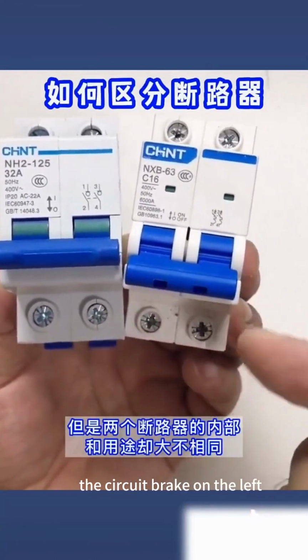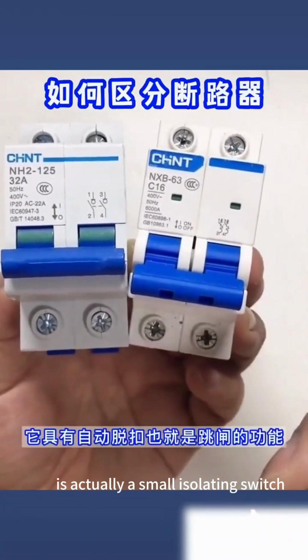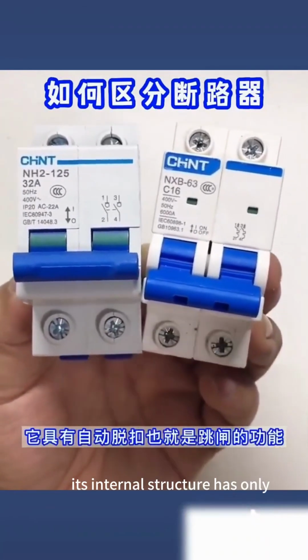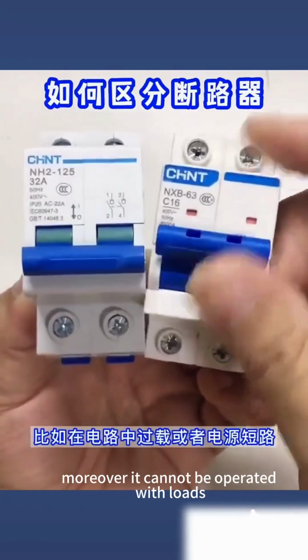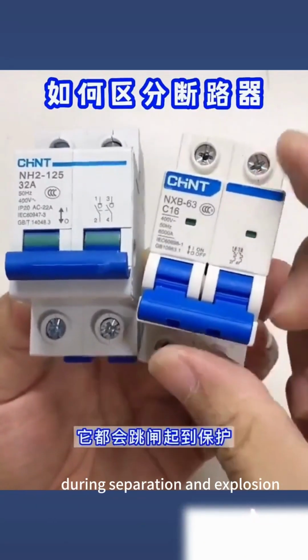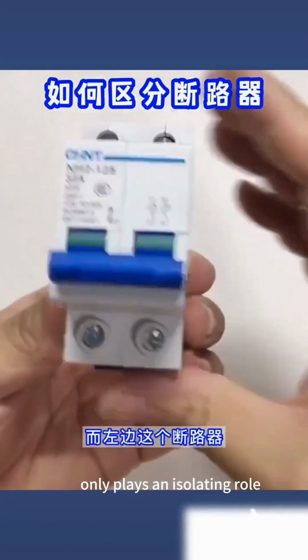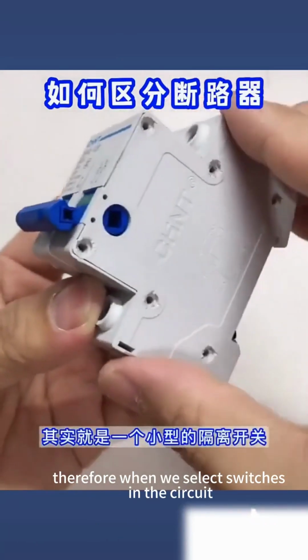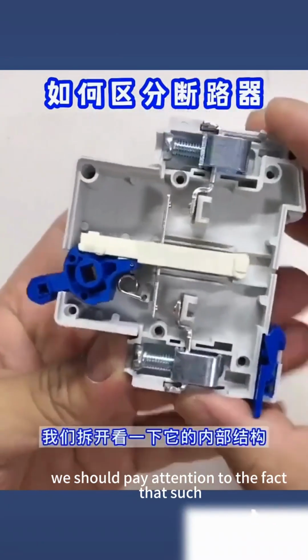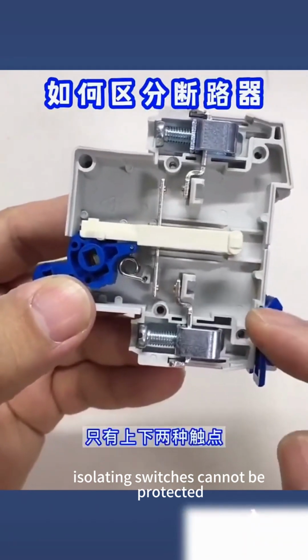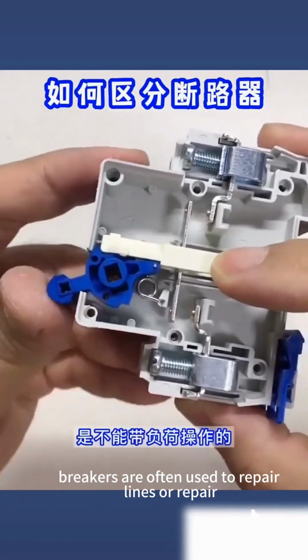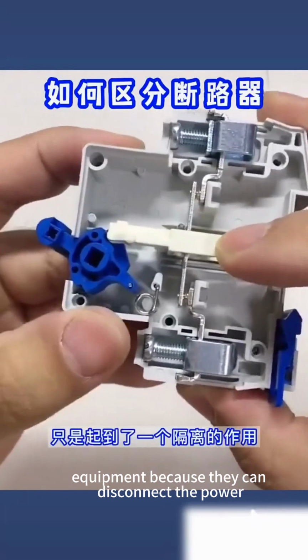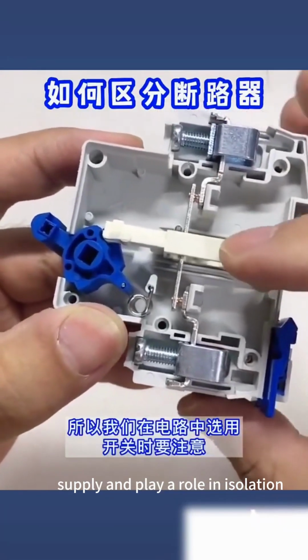The circuit breaker on the left is actually a small isolating switch. Let's take a look at it. Its internal structure has only upper and lower contacts. Moreover, it cannot be operated under load to break the circuit, and only plays an isolating role. Therefore, when we select switches in the circuit, we should pay attention to the fact that such isolating switches cannot provide protection. Isolating switches are often used to repair lines or equipment because they can disconnect the power supply and play a role in isolation.